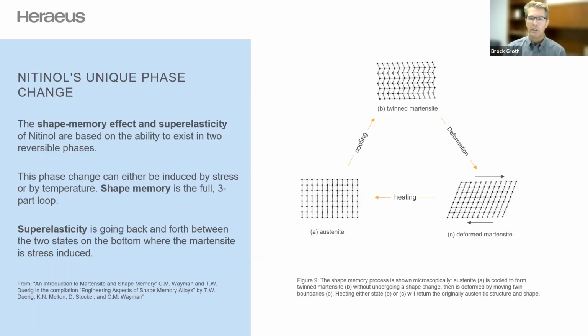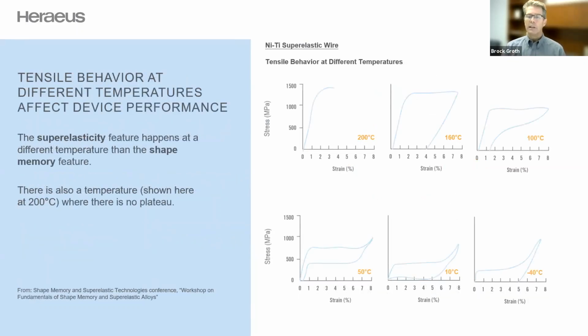So that's a little bit of superelasticity versus shape memory and the temperature effect of the two relative to the transition temperature. So if we go to the next slide. And so diving in, combining what we've looked at in the stress strain curves and what we've talked about in the temperature relationship between the transition temperature and the environment that the device is performing in. Now we're combining those, and what we have here is a series of 6 graphs of the same hypothetical material being tensile tested at different temperatures.